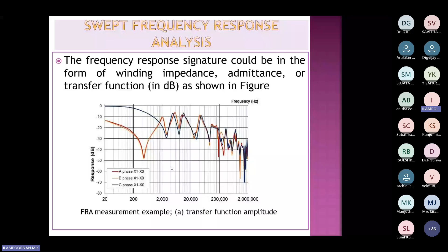I take a transformer, apply a range of frequencies in the actual winding, and take multiple waveforms of the currents and record the response. This is the frequency response of the transformer, taken across three phases - when I connect one phase, the other two phases are connected to ground along with the ammeter. So it's a kind of response. I'm not going deep into it; you can verify, there are a lot of papers done about this.